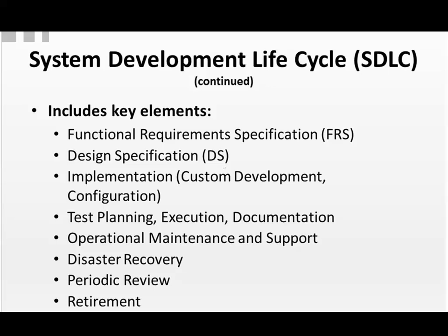Once it's in operational maintenance and support, you need to have all of the operational maintenance logs, all of the procedures, all of the SOPs, everything that's required to document that the system is being maintained in a validated state. So you want to record your preventative maintenance, your unscheduled maintenance, any disasters that happen, how you recover the system, your backup and recovery and archival, and finally your system retirement.